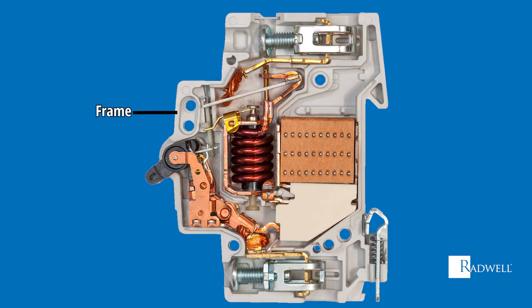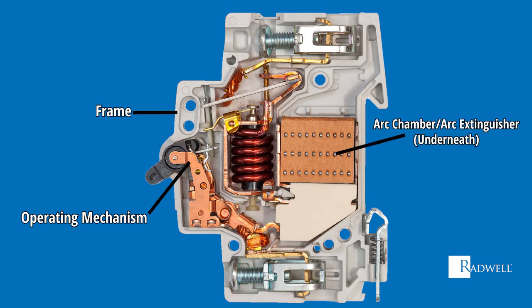Next is the operating mechanism. This component opens and closes the contacts, which is basically turning the circuit on and off. When an arc is created by the interruption of the circuit breaker, it will need to be extinguished. That function is carried out by the arc extinguisher.